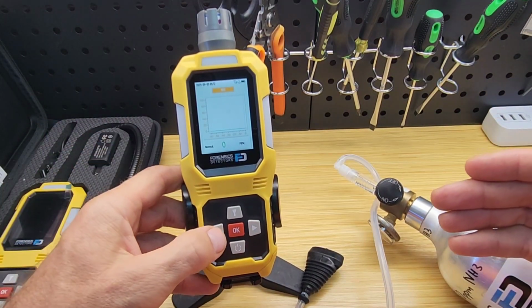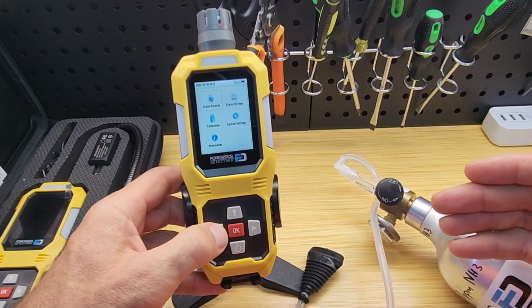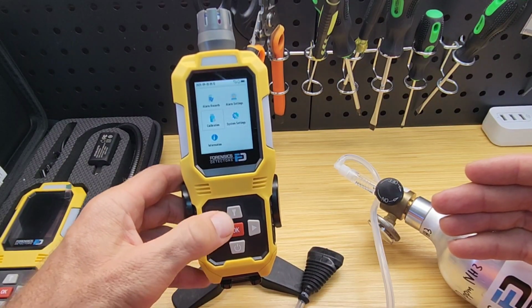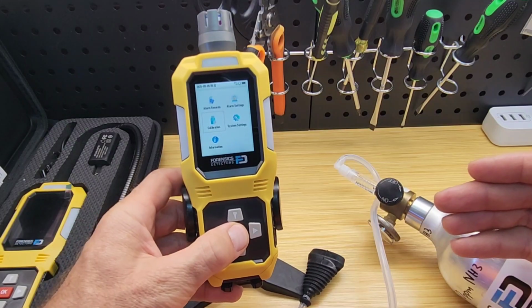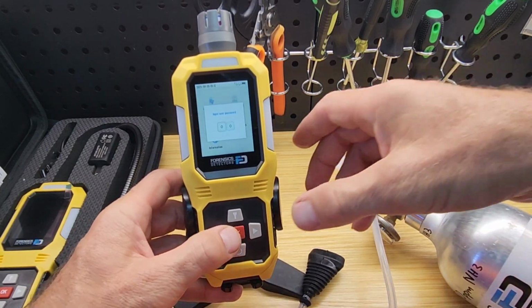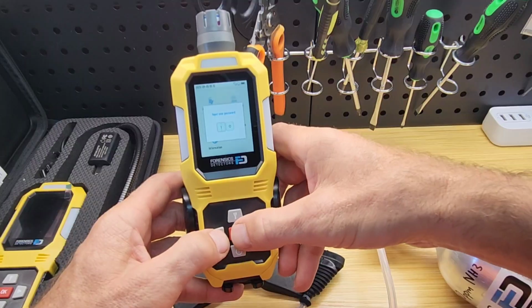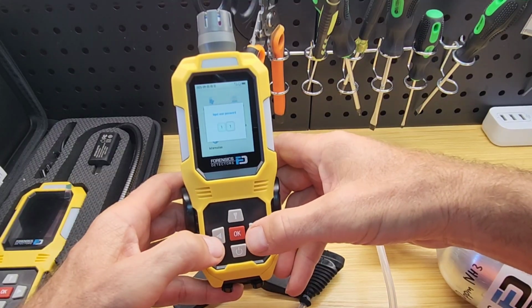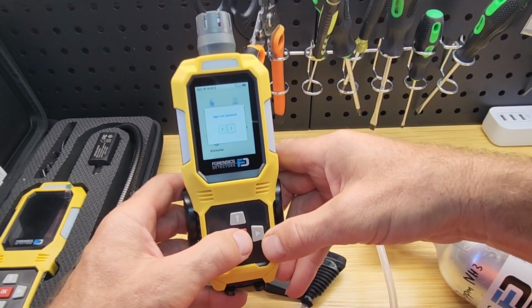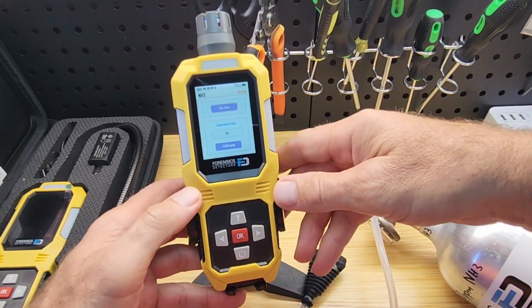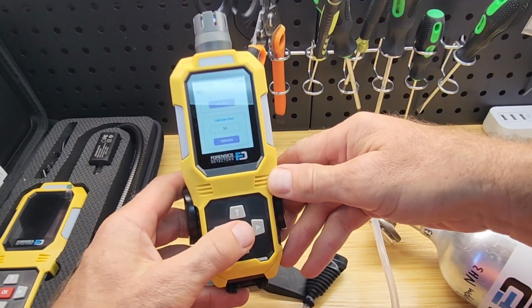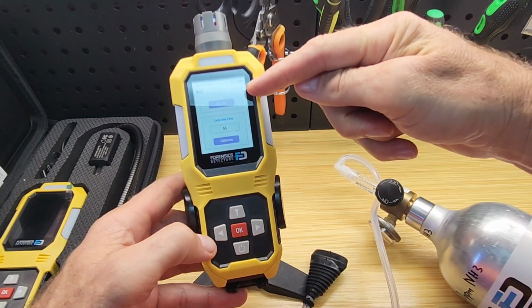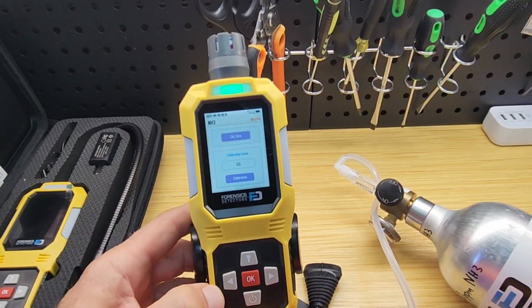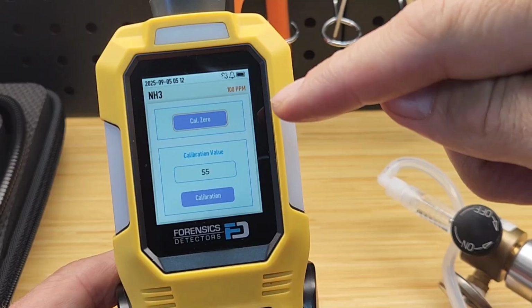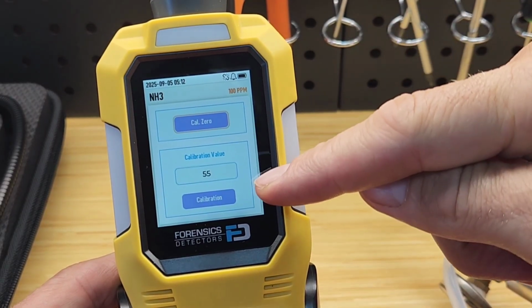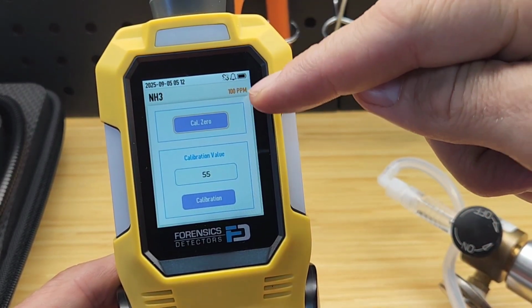Make sure the unit is in fresh air, ideally outdoor air, and you will then go into the menu by pressing OK. Click on OK for calibration. Click on the password, it's 11, and use the left and right to make the numbers go up and down, and use the middle OK to enter the input. A long press means enter, and then you have two options. The cal option over here, let's zoom in so no one gets confused. You have your cal 0 option and you have your calibration option. Step number one focuses only on the cal 0 option.